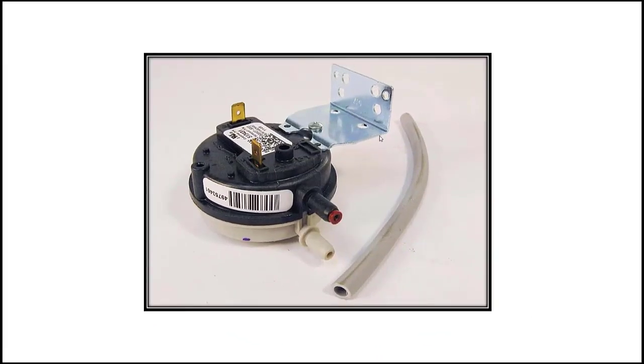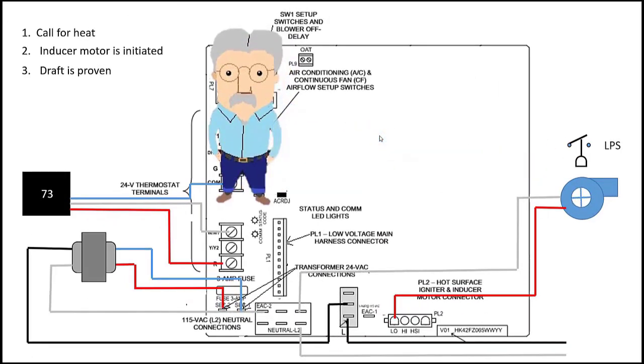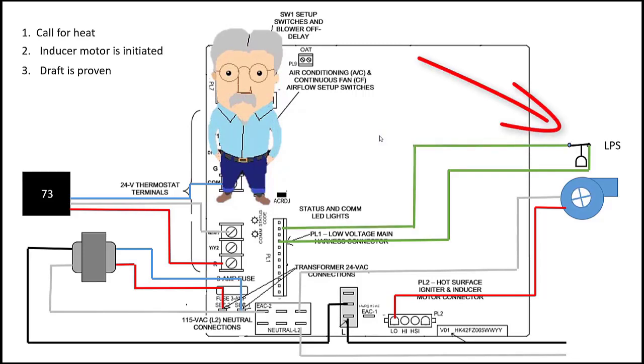We do that with a pressure switch. Here's what a pressure switch looks like. Here's our pressure switch and let's wire that thing up. When there is enough air flowing through the furnace that we know will have complete combustion, that pressure switch closes. That tells the circuit board it's time to go on to the next step in the sequence.